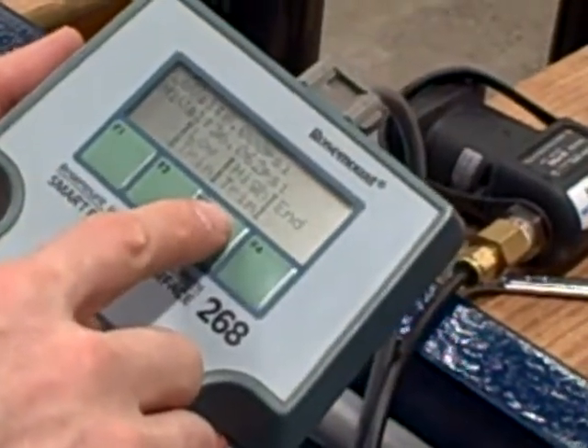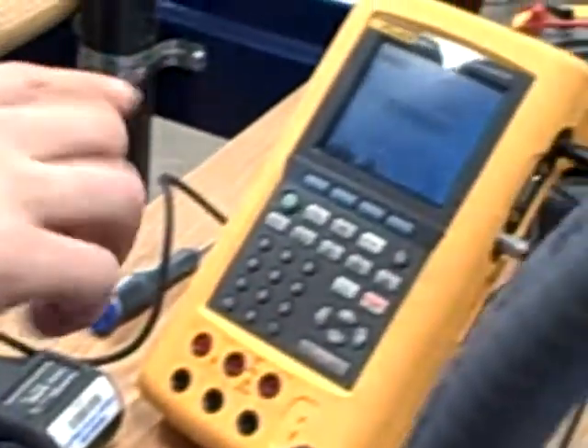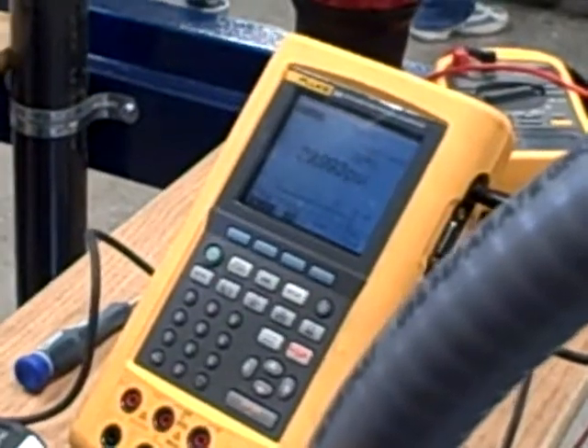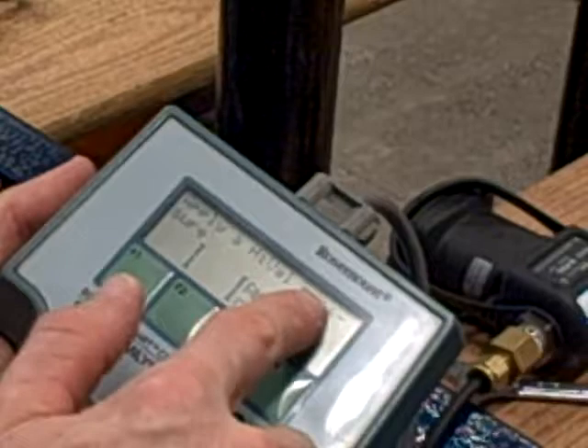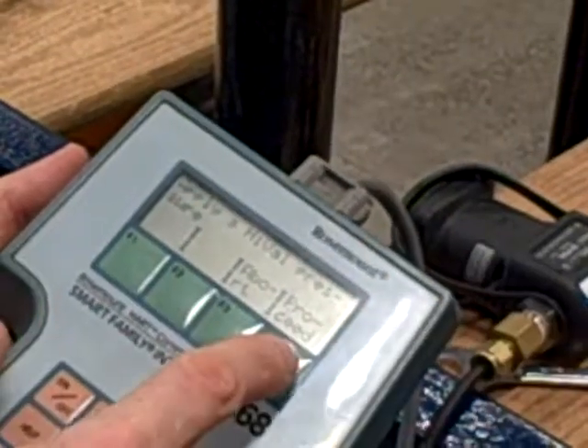I'm going to do a high trim. Notice we already have our pressure connected, 29.993 psi. It's settled there. It's very stable, so I'm very comfortable with that. I'm going to press the high trim button. Apply a high value pressure. Well, we already have. I will proceed.